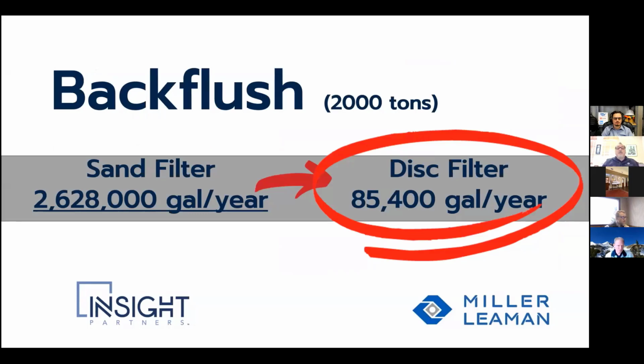For example, we talked about backflush water use. On a standard 2000-ton cooling tower, with the disc filter and the sand filter backflushing an equal amount of time, you can look at this. The sand filter will use over 2 million gallons per year of water, where the disc filter will use around 85,000 gallons of water a year.